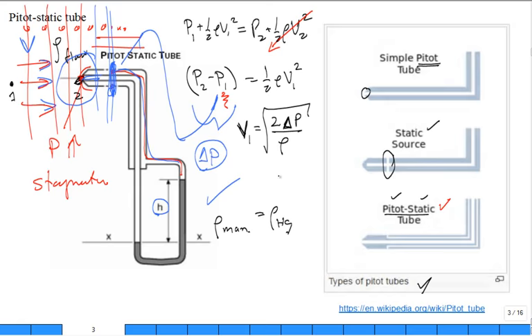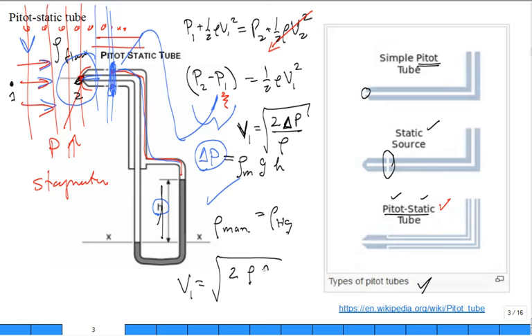If you're using a manometer, ΔP = ρ_manometer · g · h. So V₁ = √(2·ρ_manometer·g·h / ρ_fluid). Don't cancel those two rho values — one is the rho used in the manometer (maybe mercury) and one is the rho of the fluid coming to rest at the tip (maybe air or water). They're different fluids.